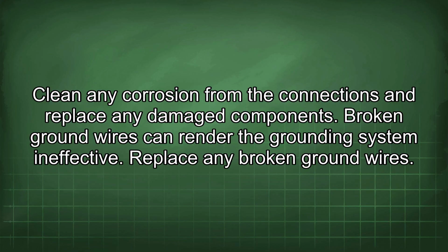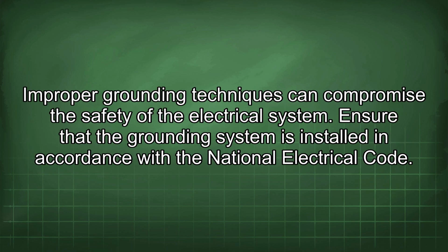Broken ground wires can render the grounding system ineffective. Replace any broken ground wires. Improper grounding techniques can compromise the safety of the electrical system. Ensure that the grounding system is installed in accordance with the National Electrical Code.